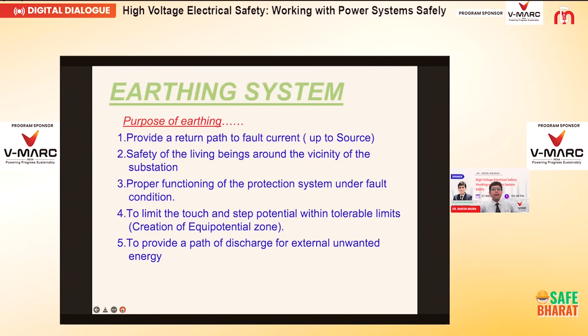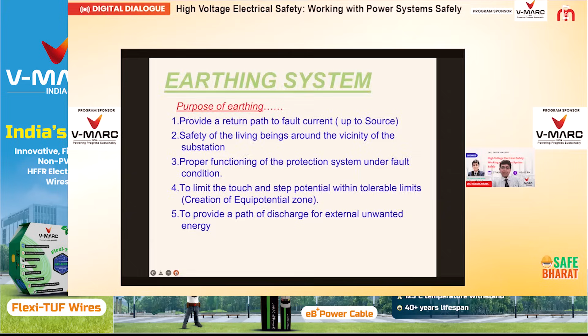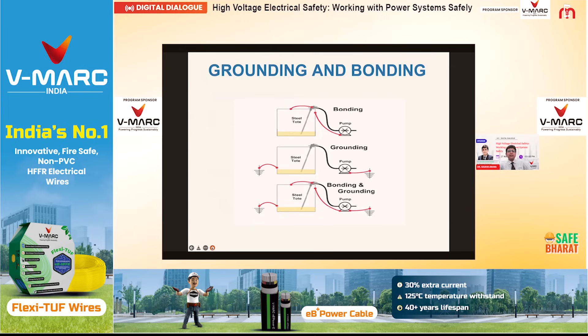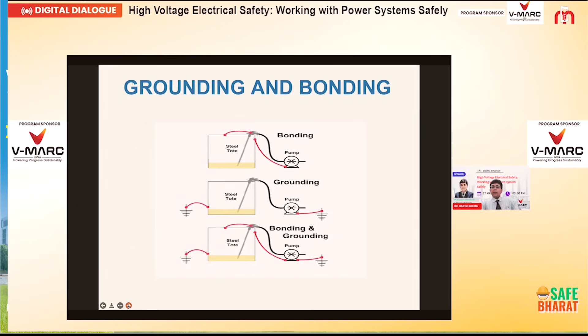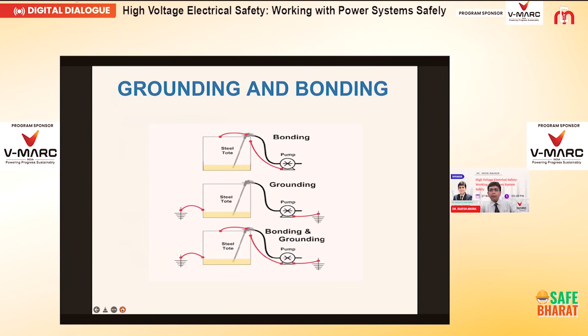Last but not the least, I have to provide a path of discharge for the external unwanted energy in the form of lightning. Apart from earthing and grounding, bonding plays a vital role. Even if you provide proper grounding systems, if it is not bonded within the system, you are not providing equipotential zones within the substations, and the purpose of earthing will be defeated. This picture shows how to do the grounding, how to do the bonding, and how to ensure both grounding and bonding in the systems you are working with.